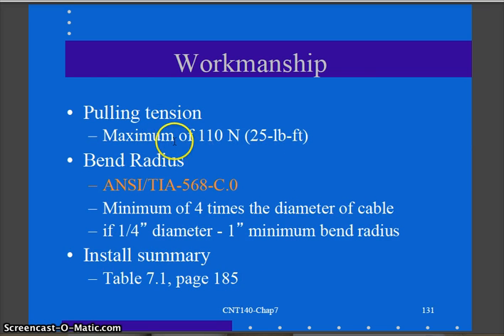As I'm routing wiring into the rack, the pulling tension limit is about 25 pound-feet of force, think of hanging a 25-pound weight on the cabling, that's a good amount of weight. So as I'm routing cabling, if it gets hung up, I stop, find where it's caught, and carefully route it so I'm not pulling on it.